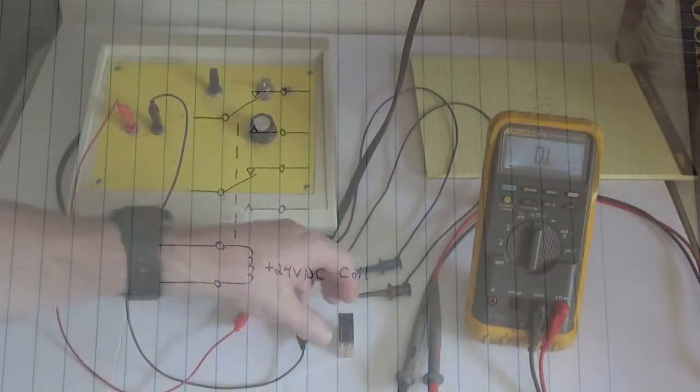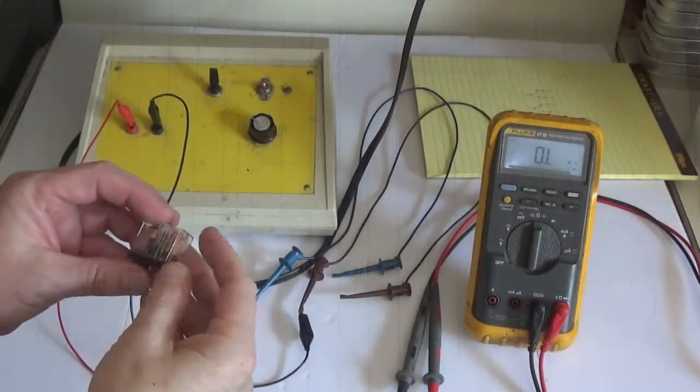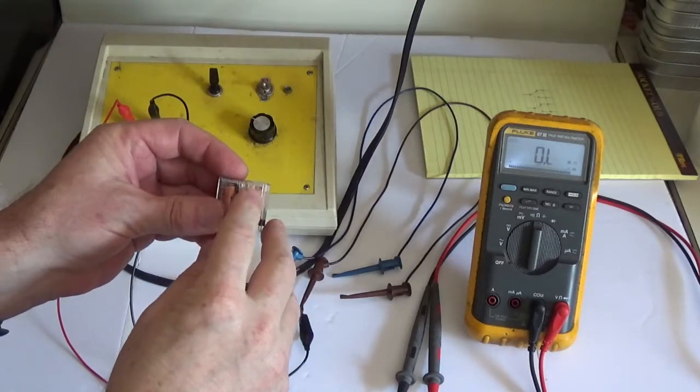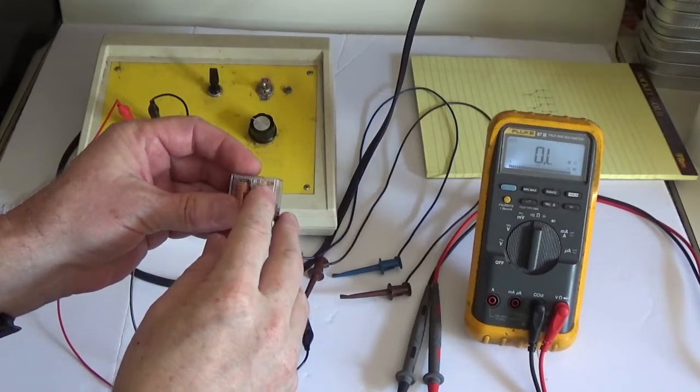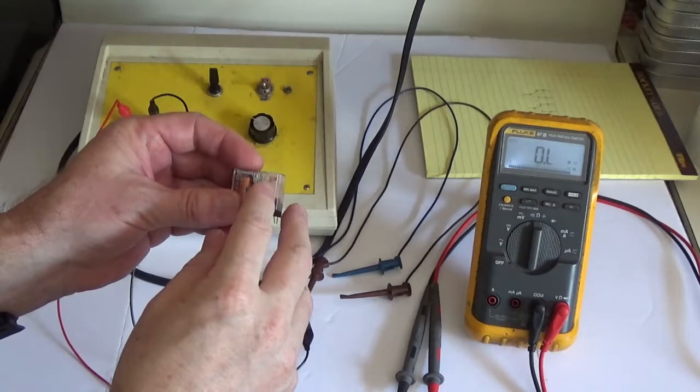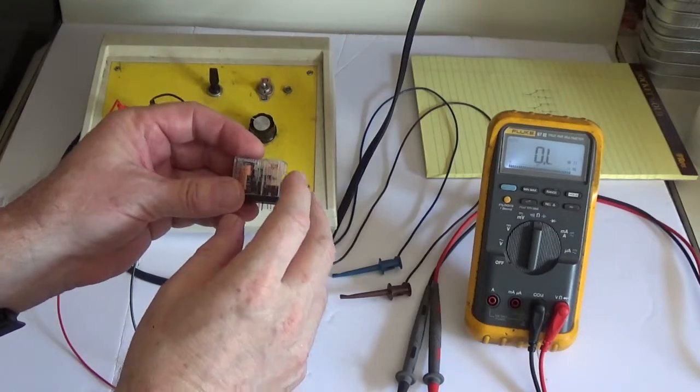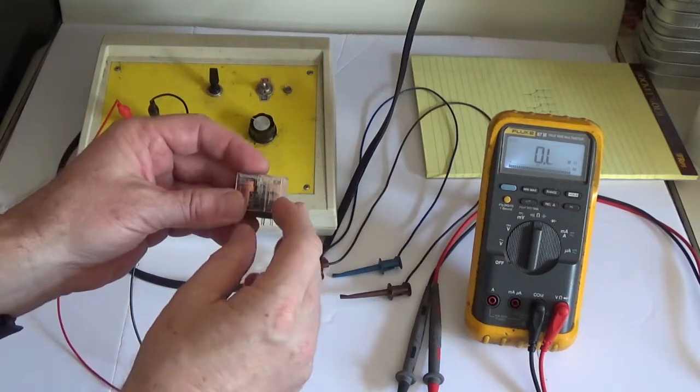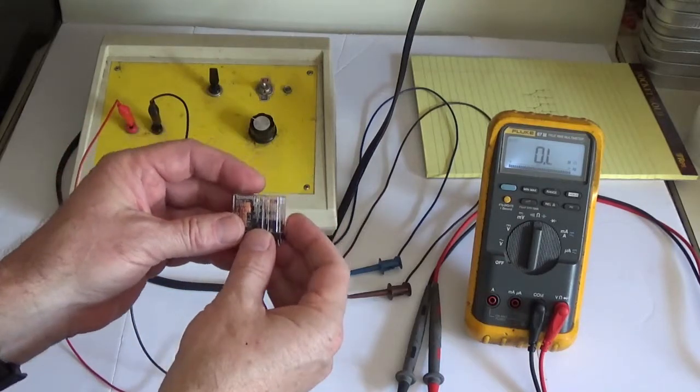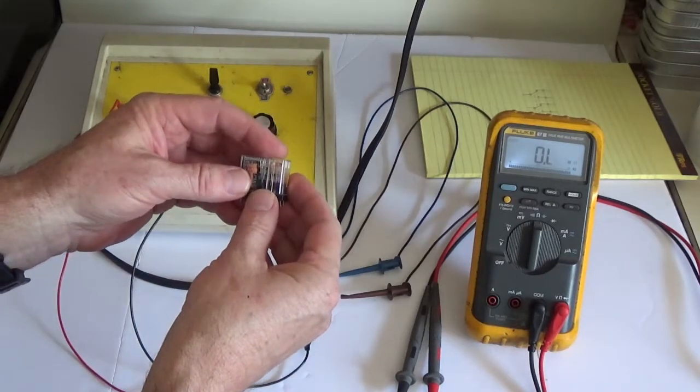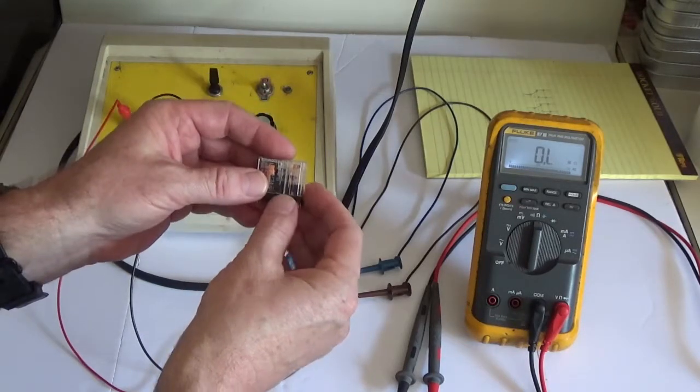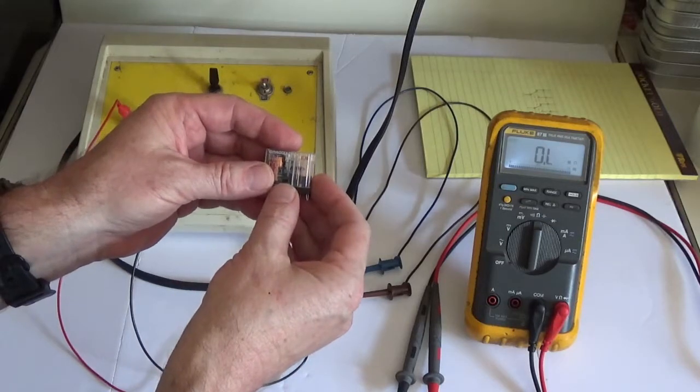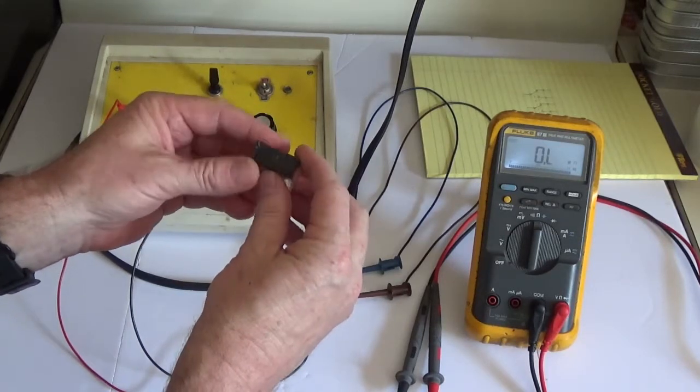Now what happens to these relays normally is that over the years the contact resistance between the normally closed or the normally open or both will become too high. They won't fully conduct. In that case, the relay either needs to be taken apart and cleaned or replaced. Here we're going to check this relay with this little setup right here.